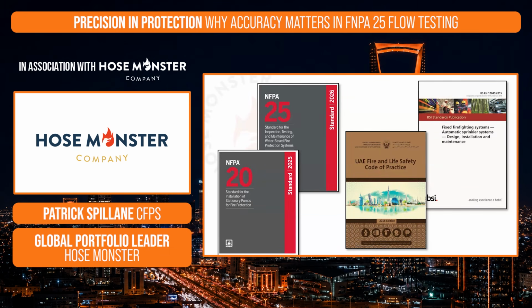We're going to be focusing a lot on NFPA 25, which is the standard for inspection, testing, and maintenance of all water-based fire protection systems. That includes sprinkler systems, fire pumps, and standpipe landing valve systems, as well as NFPA 20, which covers the installation of stationary fire pumps. The UAE follows the Fire and Life Safety Code of Practice by the Civil Defense, and that code book also references NFPA 25 and 20 when it comes to fire pump testing.